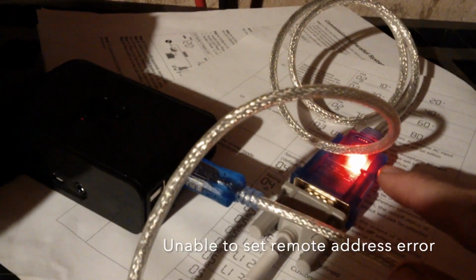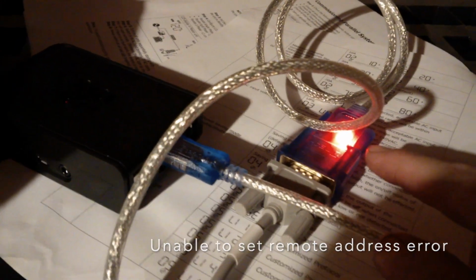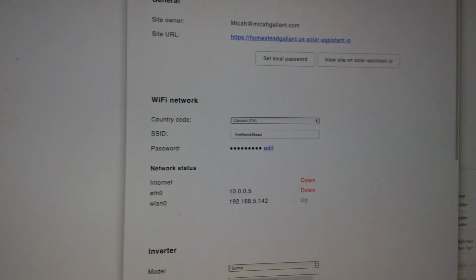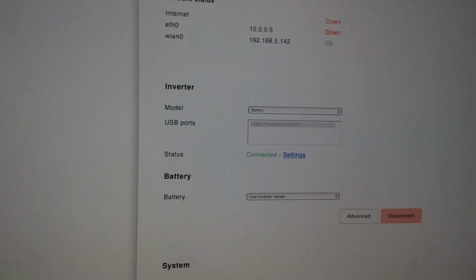So what was happening, this was showing all green, all lights solid, red, yellow, and green, and it wouldn't start, and so it showed "unable to set remote address."